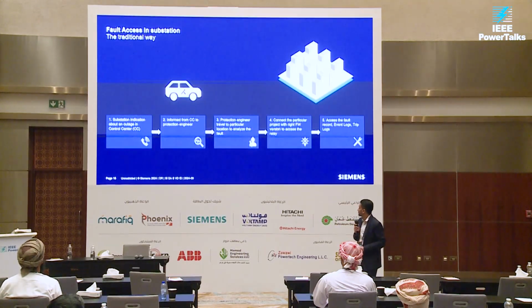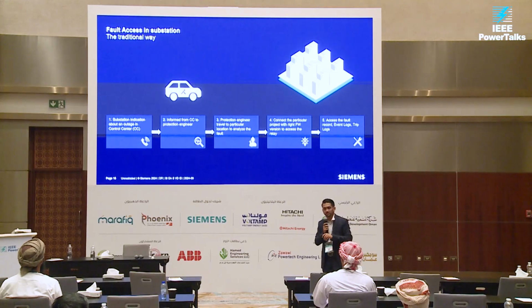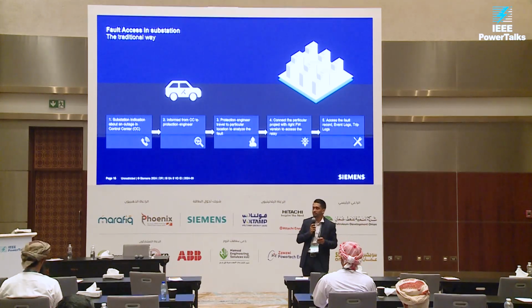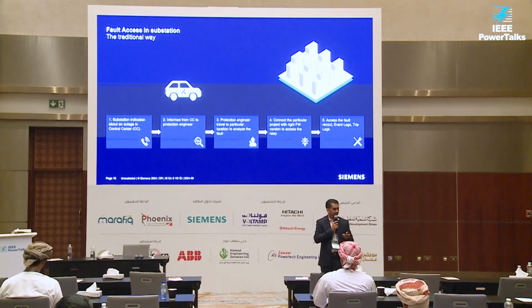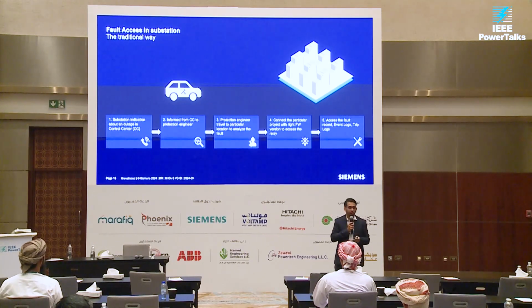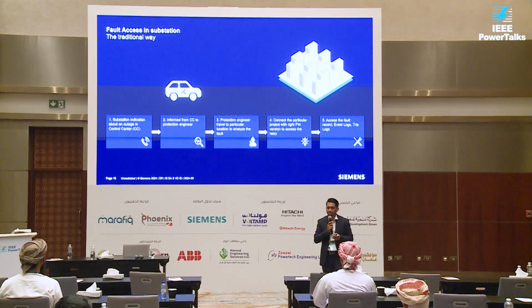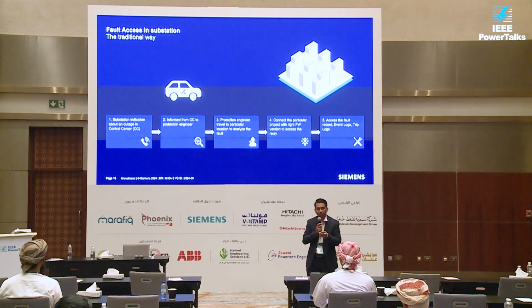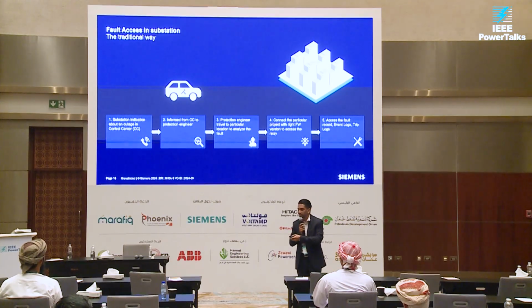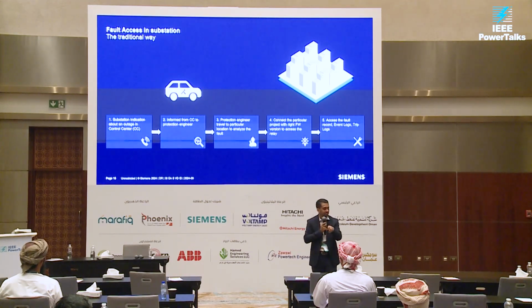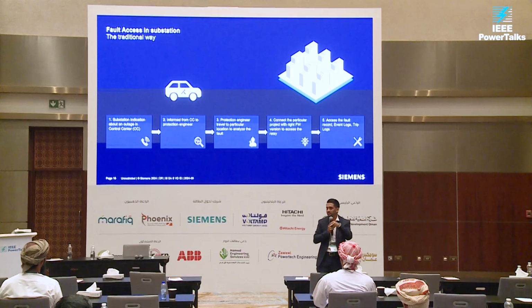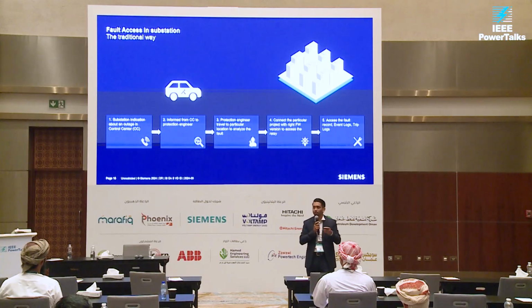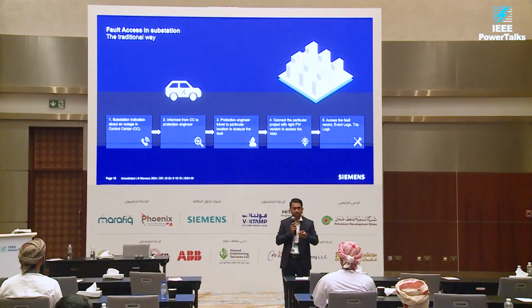So let me go here. If I take a fault in the substation, when there's a fault, for example, if you have a SCADA system, the SCADA system says, okay, this particular bay has tripped. But now the challenge is they do not know exactly what kind of fault it is, what fault current the fault happened with. So then you need to send a protection engineer to the site. He connects to the relay, then he downloads the fault records and then carries out the fault analysis. What if all this data is available on his phone? Like he has access to this application. He just logs into the application.